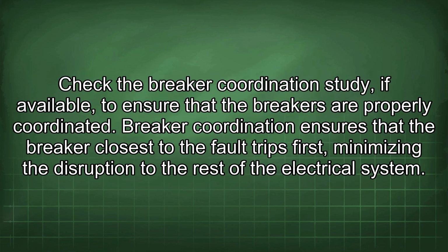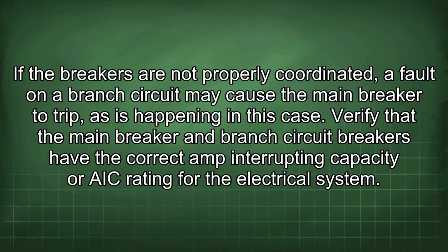Check the breaker coordination study, if available, to ensure that the breakers are properly coordinated. Breaker coordination ensures that the breaker closest to the fault trips first, minimizing the disruption to the rest of the electrical system. If the breakers are not properly coordinated, a fault on a branch circuit may cause the main breaker to trip, as is happening in this case.